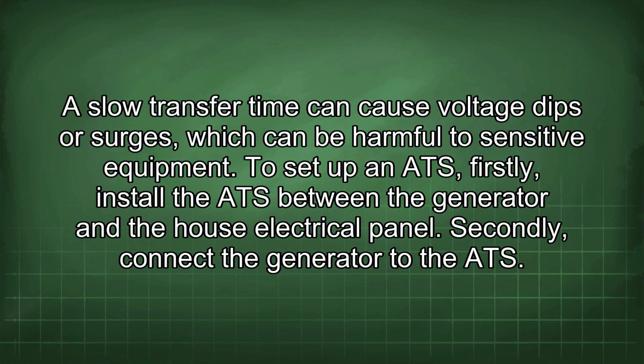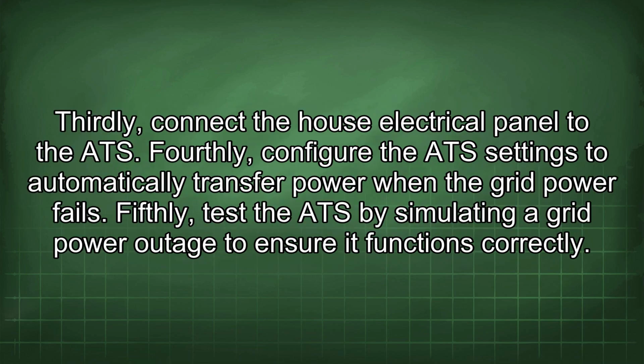To set up an ATS, firstly, install the ATS between the generator and the house electrical panel. Secondly, connect the generator to the ATS. Thirdly, connect the house electrical panel to the ATS. Fourthly, configure the ATS settings to automatically transfer power when the grid power fails. Fifthly, test the ATS by simulating a grid power outage to ensure it functions correctly.